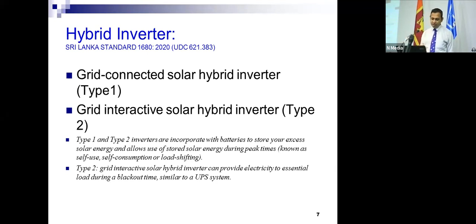Type 1 and type 2 inverters are incorporated with batteries to store your excess solar energy and allow use of stored solar energy during peak times—known as self-use, self-consumption, or load shifting. But only type 2 allows grid-interactive mode, where the inverter can provide electricity to essential loads during a blackout. Type 1 cannot do this.